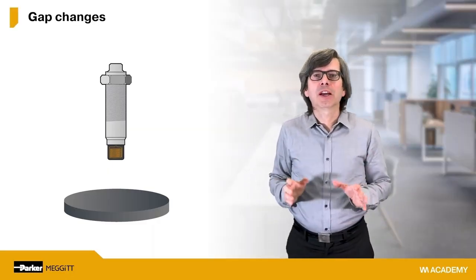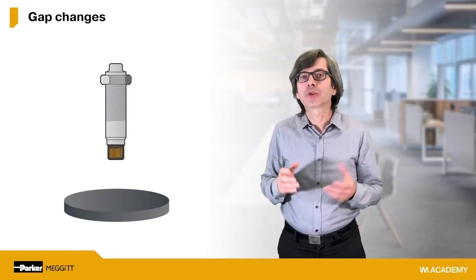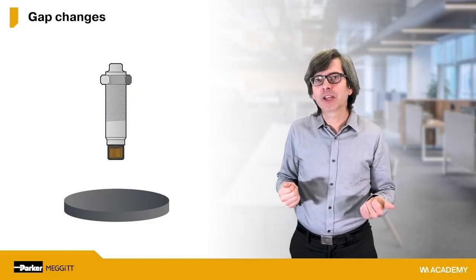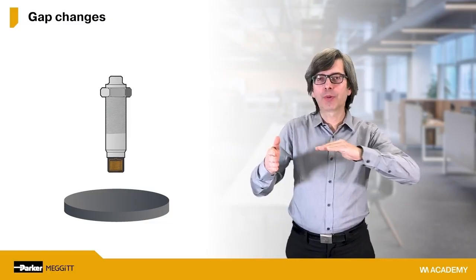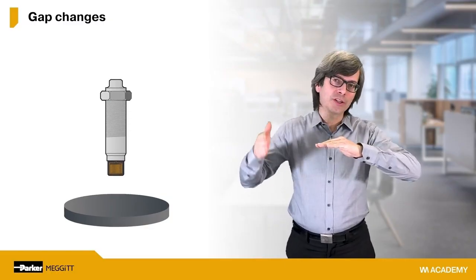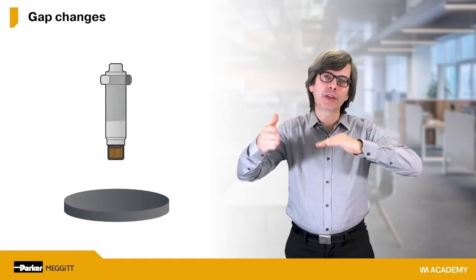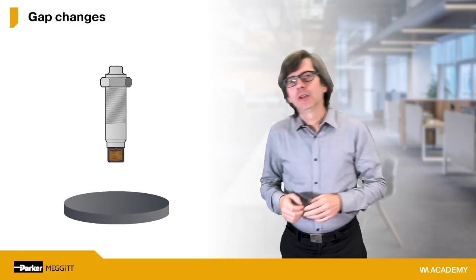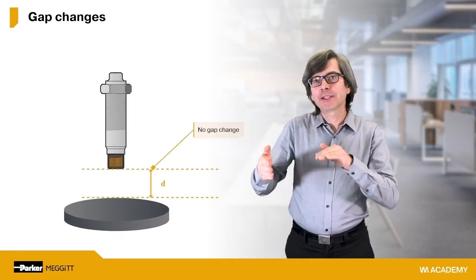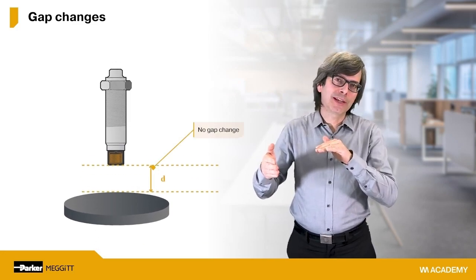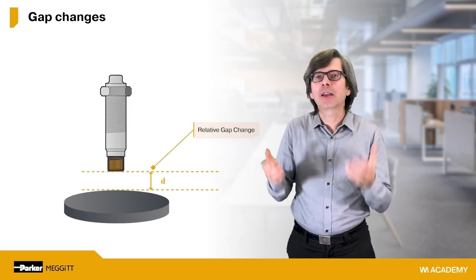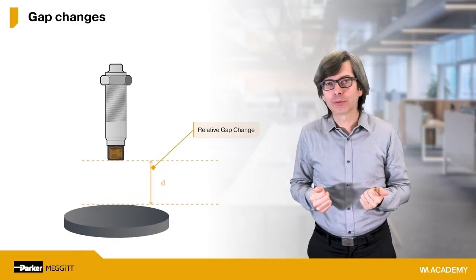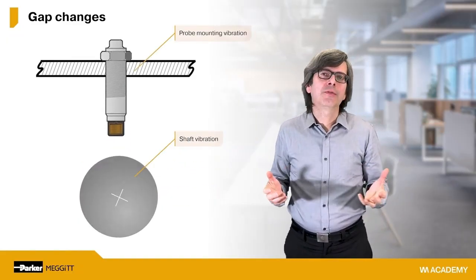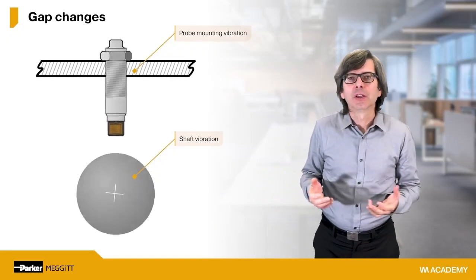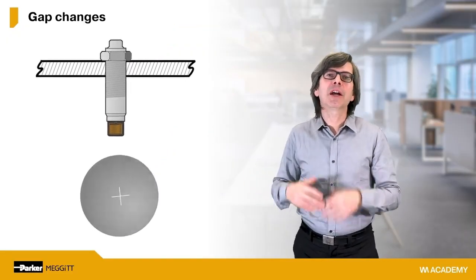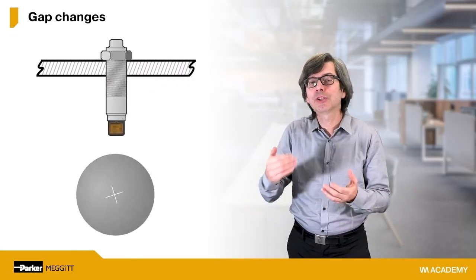Another important aspect to understand of proximity probe measurements is that the gap can change due to motion of the probe itself, motion of the target, or motion of both in parallel. Since the probe senses only the relative change between itself and the target, it's sometimes called a shaft relative probe. Generally, for vibration measurements, we assume that the motion of the shaft is much larger than the motion of the casing to which the probe is attached.